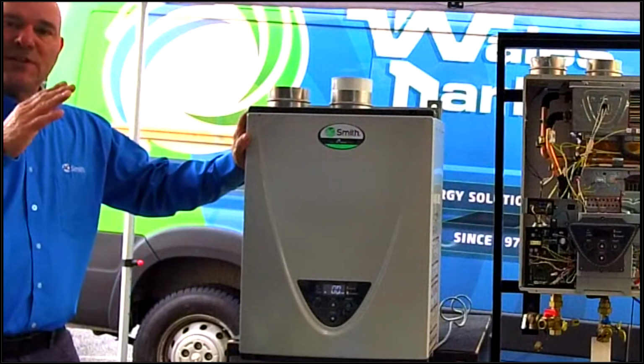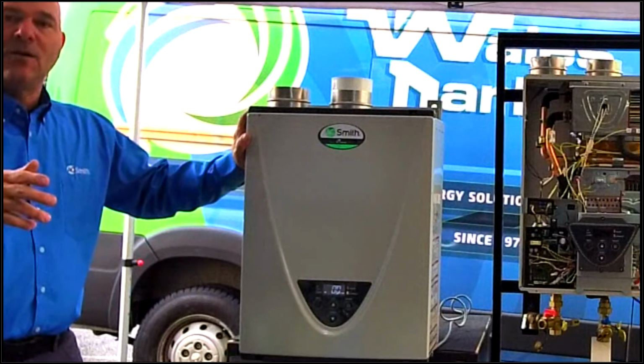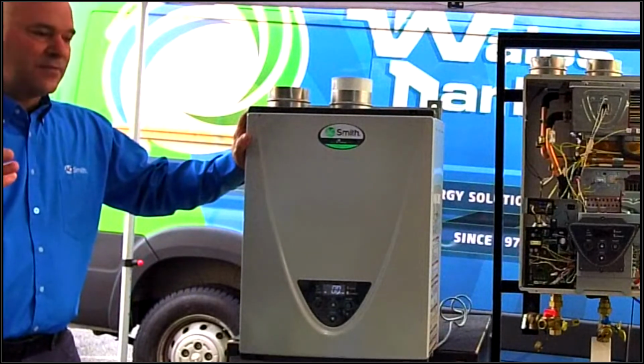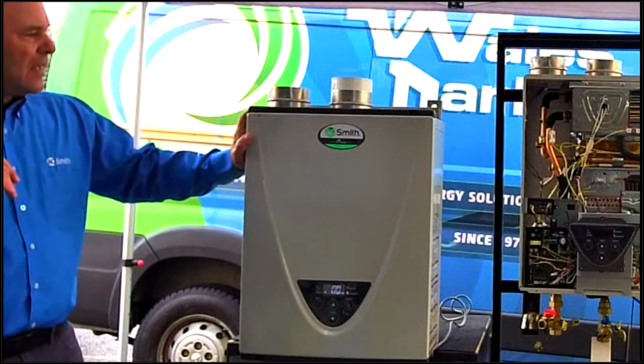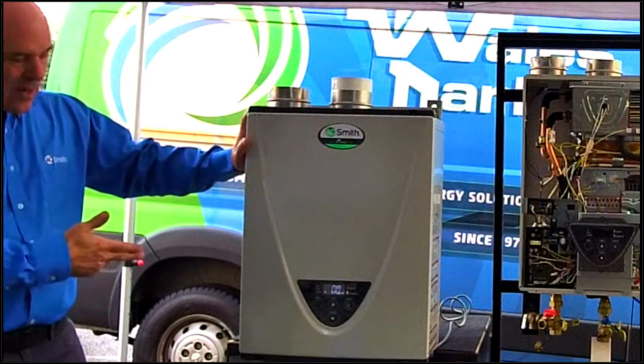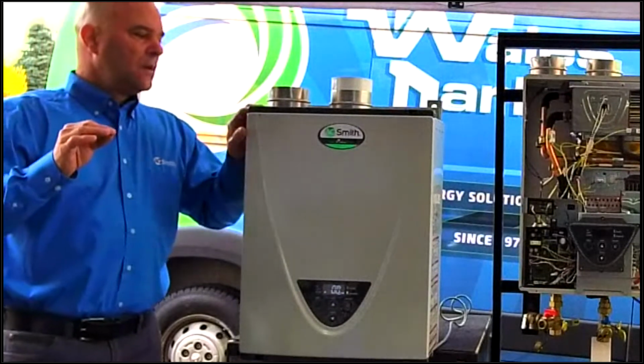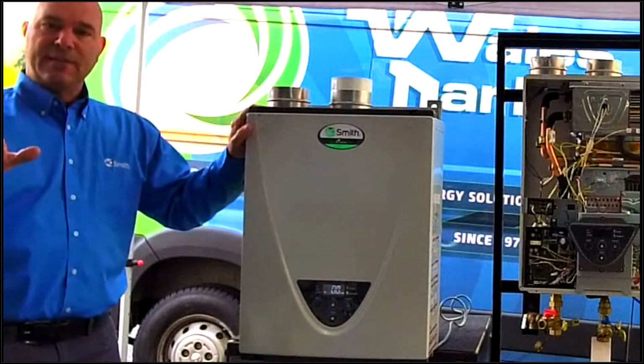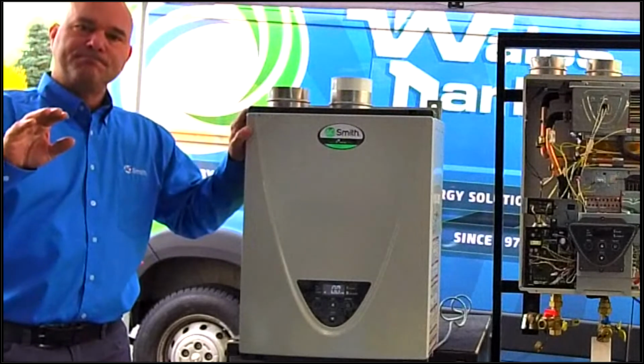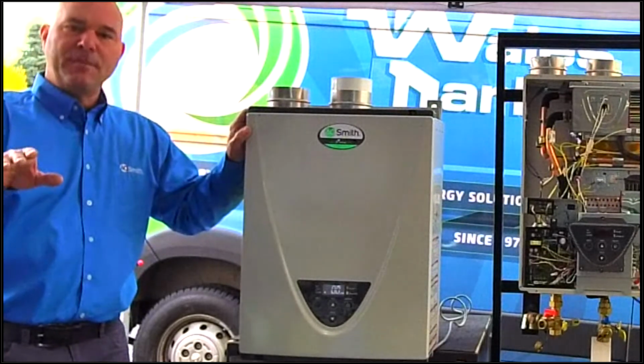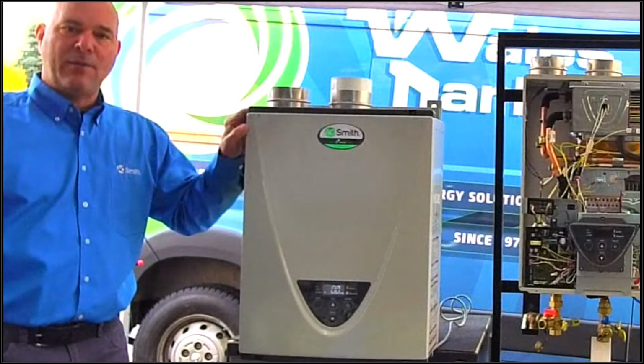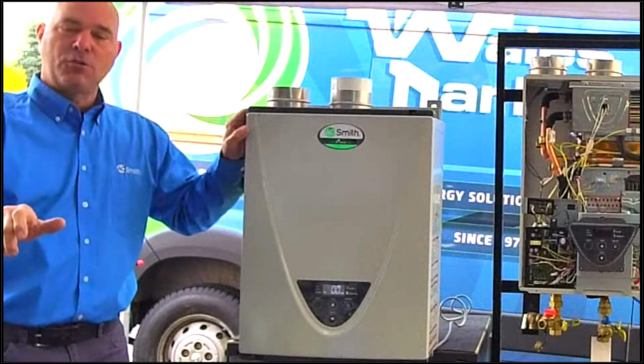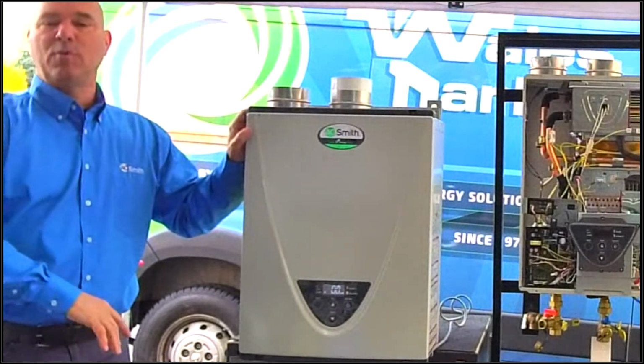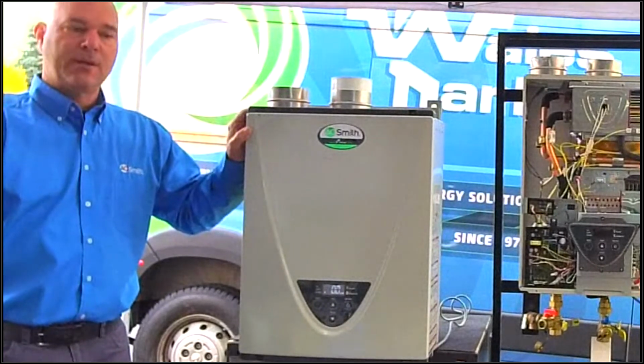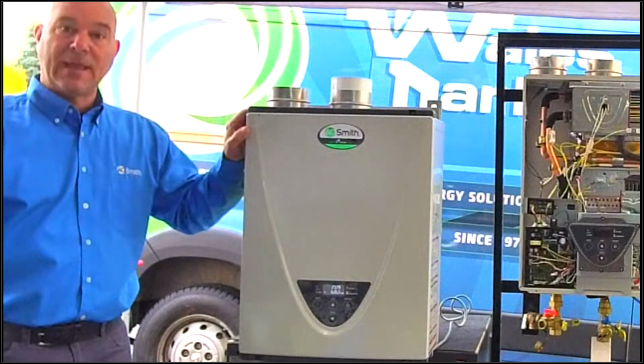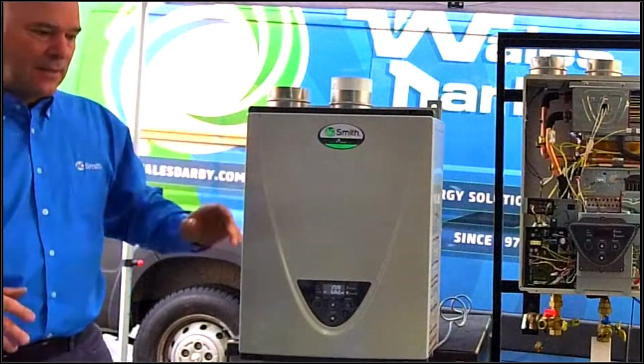That flow rate is going to be a moving target based upon what's going on in the home. Is it 1 shower? Is it 2 showers? Is it 5 showers? Now, we talked about flow rates earlier, and we're on flow rates right now. I want to clear up a myth that's in the industry. I have the ability to run a tank style water heater out of hot water, right? A long draw, a deep draw. I can pull all the hot water out of that water heater in a matter of, let's call it 7 minutes or less, depending on what the draw is.